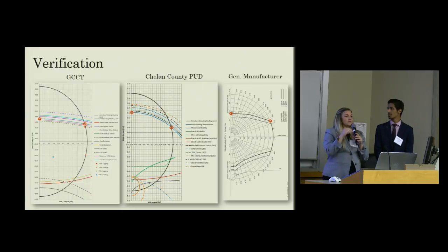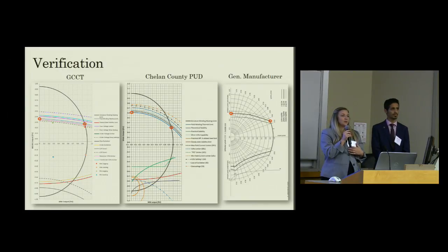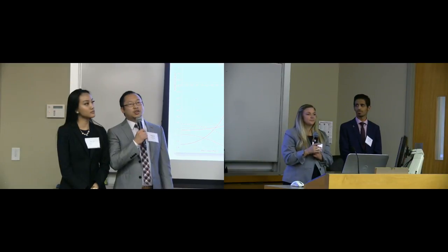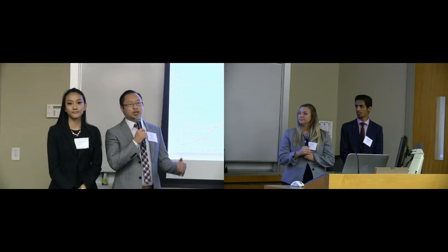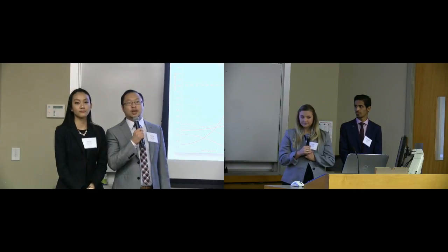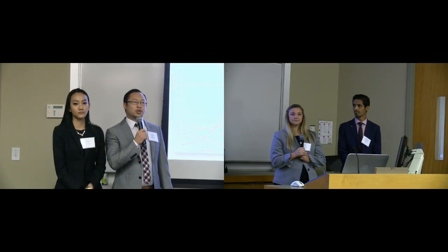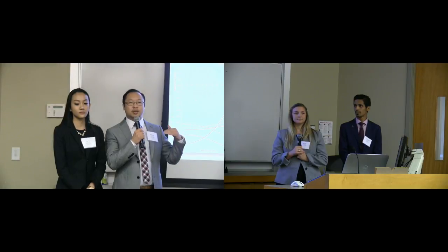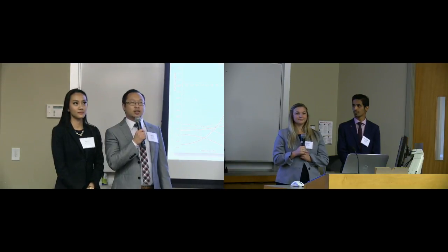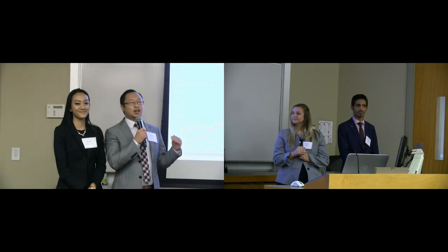Most of our curves, with the exception of the loss of field zones 1 and 2, stem from the generator capability curves. So once we verified those, all the others are just varying magnitudes of those curves, so we could pretty well assume their accuracy. We chose 5% accuracy because when reading through a bunch of NERC recommendations, they actually recommend coordinating plus or minus 5%, so we thought that in order to allow coordination, we should be at least at 5%.